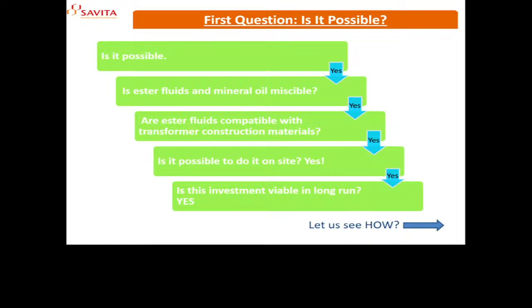And how many of you know what ester oil is, or that there is an ester oil alternative to mineral oil? Okay, this is encouraging for me. So first of all, is it possible? The answer is yes. Then, are these ester fluids miscible with mineral oil, because you have to remove the mineral oil and put something else, but is it miscible? Because there will still be residual mineral oil in the system.